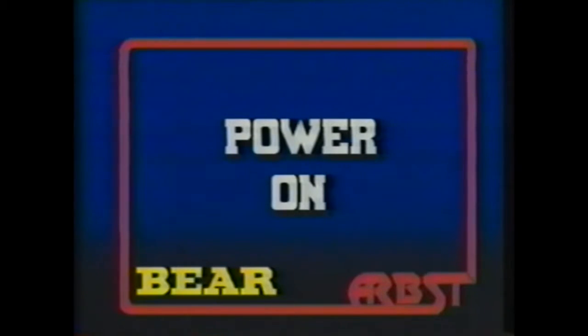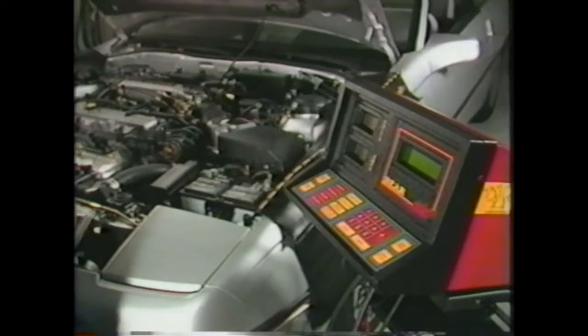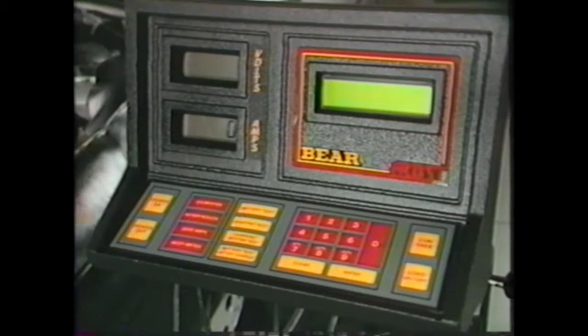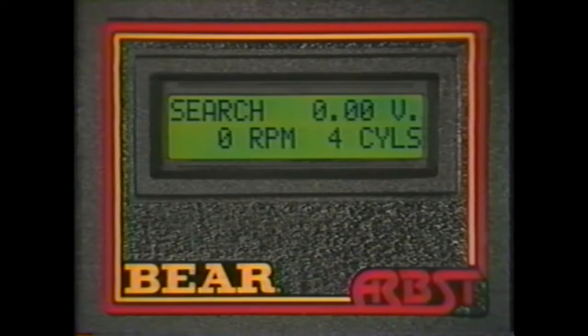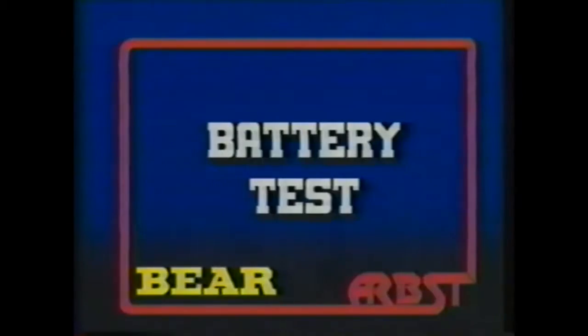Since ARBST is so easy to use, let's begin testing right away. Press the Power On key to turn the tester on. The main display on the tester shows messages and instructions to be followed during automatic testing. When the tester is turned on, it runs an automatic self-check. Then the multimeter function comes up on the display. We will talk about the multimeter later, but right now we're going to run an automatic battery test.